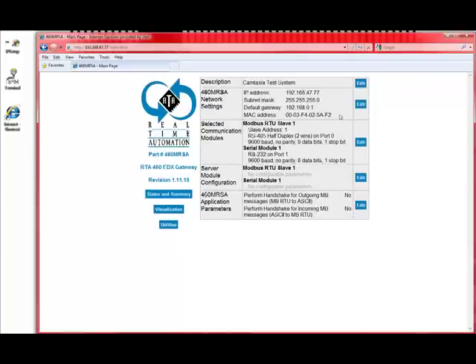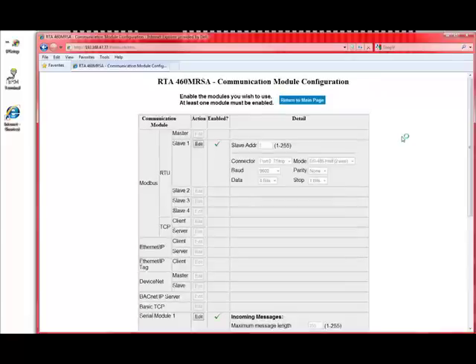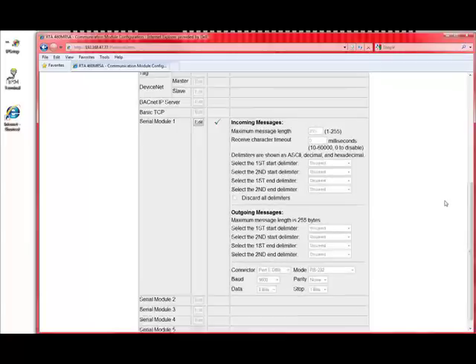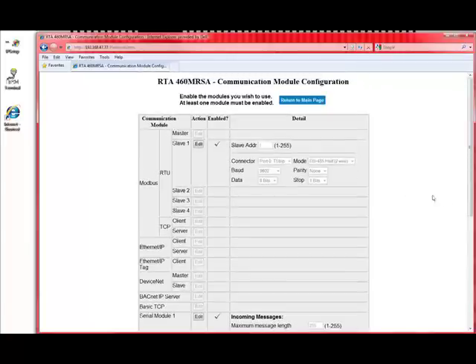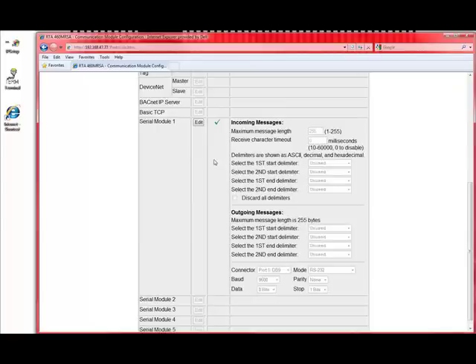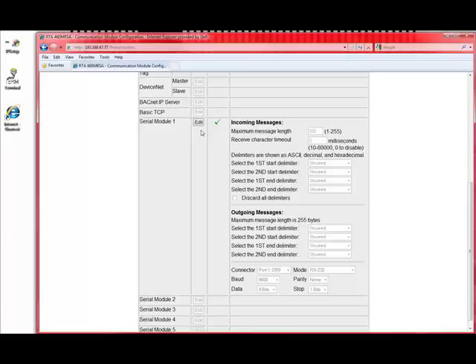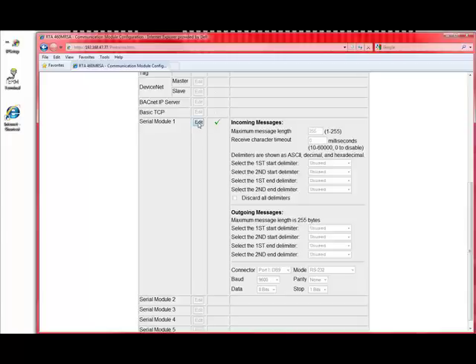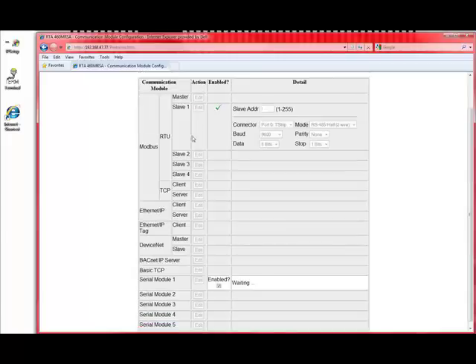The third thing we do now is we select the communication modules. What we find is that there's only two communication modules to select. Everything else is grayed out, can't be changed. Modbus RTU is selected, and the serial module is selected because that's what we're doing. We're moving serial ASCII in and out of a Modbus RTU slave. So the serial module, we're going to go ahead and edit that and configure it. This is the next step that you would do is configure the serial module.